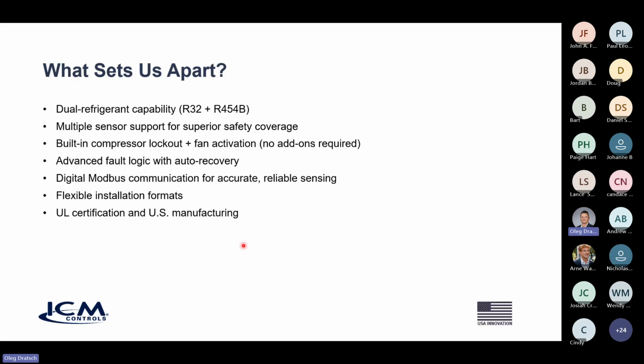This will cover both. So again, built-in compressor lockout, fan activation. So there's no extra relays or anything that you have to put on board. It's going to lock out your compressor in under 5 seconds. It's going to activate that fan to expel the refrigerant leak in under 5 seconds. And also it's got Modbus communication. So that's what we use for the quick communication between the sensor and the board. And it is UL certified and manufactured here in the United States.